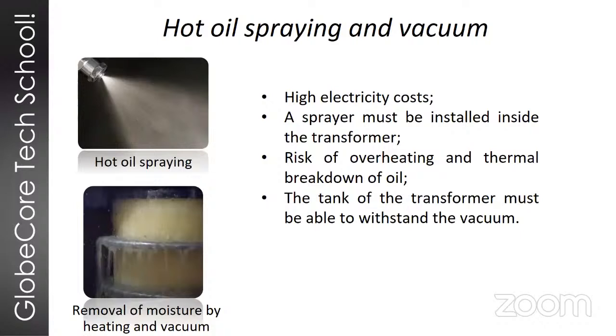This method is quite versatile, and according to our classification, it works for just about any type of oil-filled transformer and for any type of service or repair shop. Again, this technology does require quite a bit of electric energy because you need to supply hot oil into the transformer at a temperature of about 100 Celsius. And another complication is that you need to install the nozzles inside the tank.